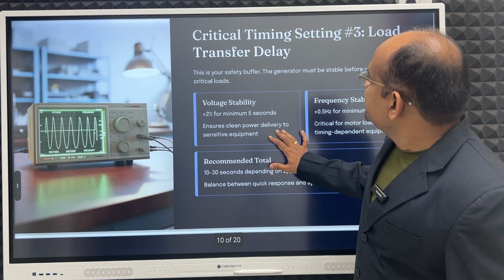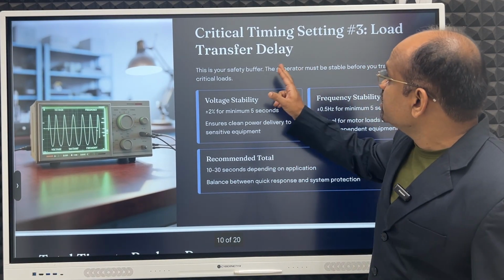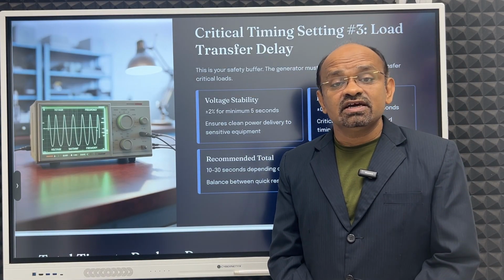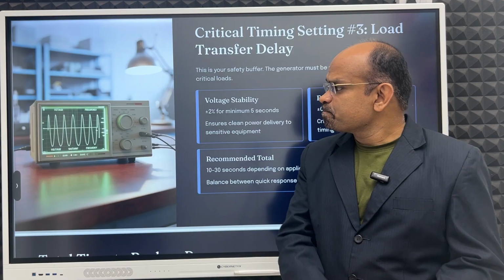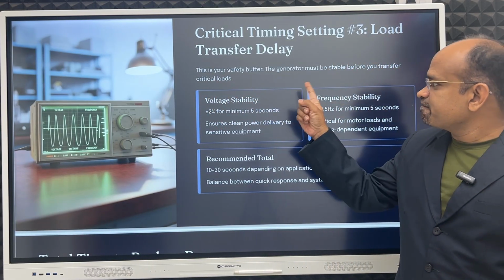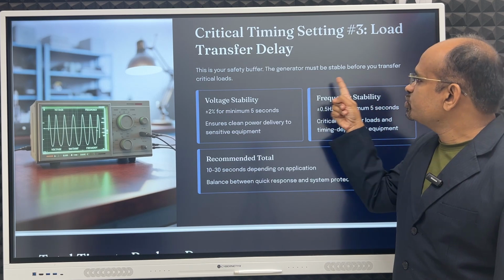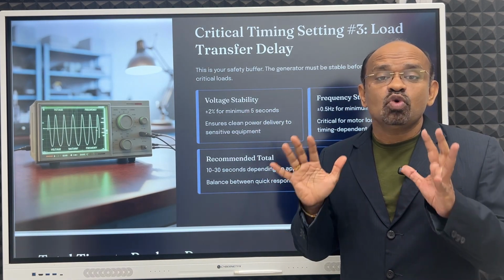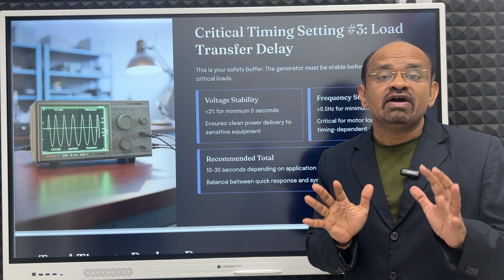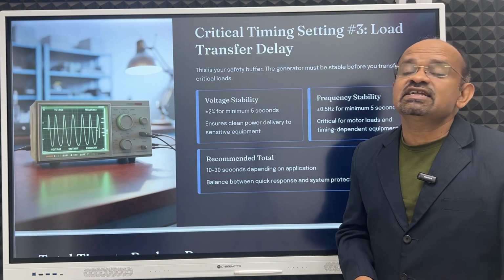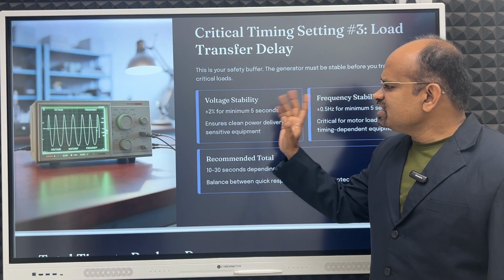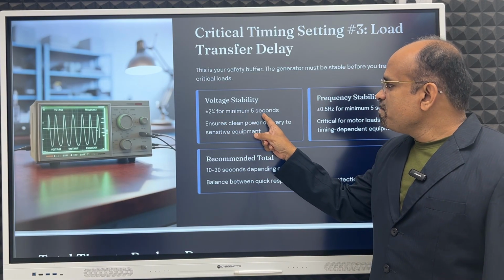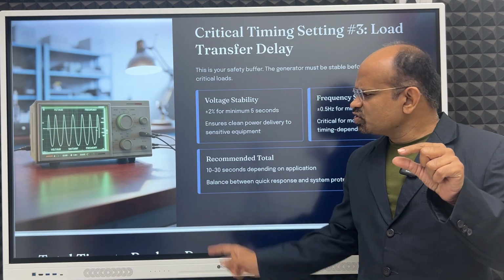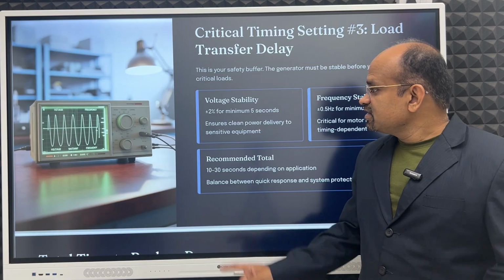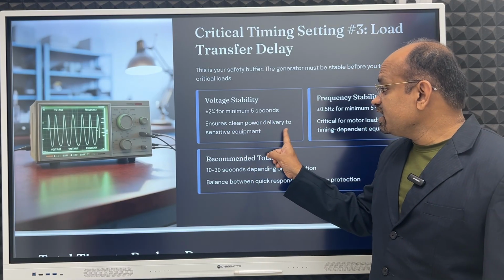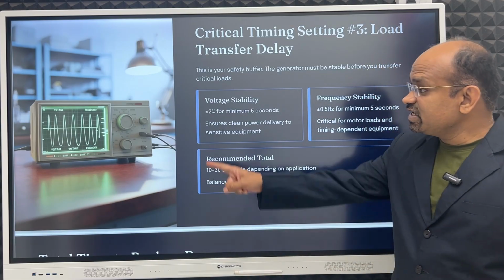Now critical timing setting number 3, load transfer delay. There should be some delay to transfer the load. This is your safety buffer. The generator must be stable before you transfer critical load. The warm up should be done, and proper speed should already be reached. Then you can easily transfer the load to the DG set. Voltage stability, plus or minus 2% for a minimum of 5 seconds. Then you're okay. It ensures clean power delivery to sensitive equipment.